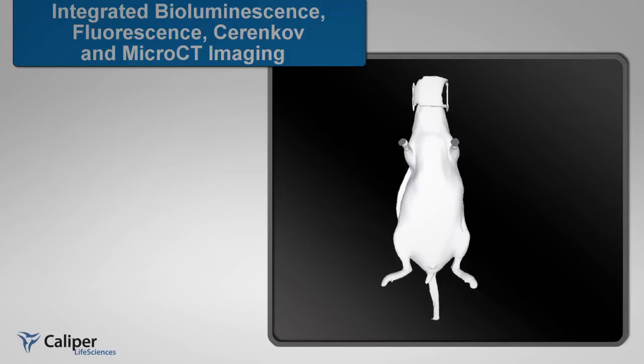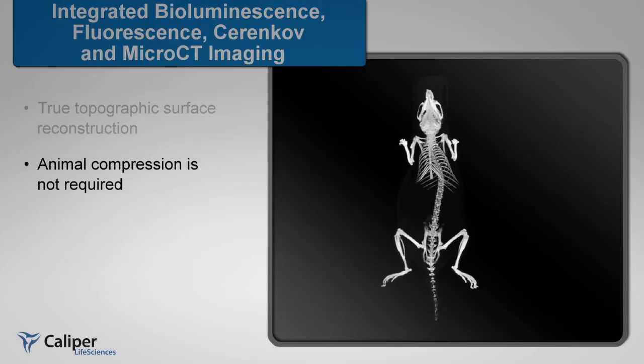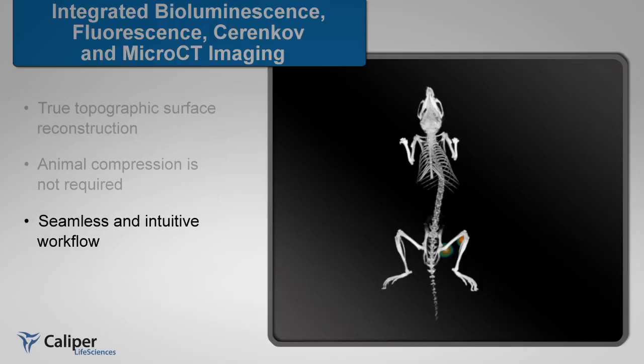IVIS fluorescent, bioluminescent, and Cerenkov 3D tomography allows for true quantitative analysis of cell number or fluorescent target. IVIS tomography does not require compression of the animal to achieve reconstruction accuracy and is the only technology that can reconstruct a 3D source from the actual 3D surface of the animal. The topographic map is created by the micro-CT scan itself.